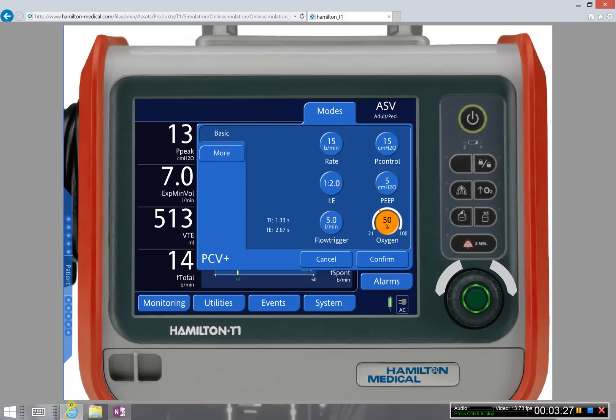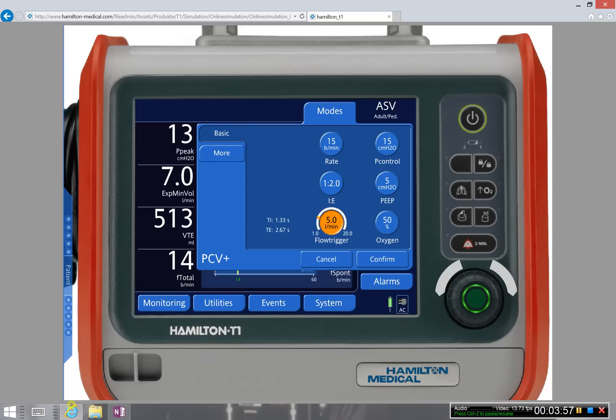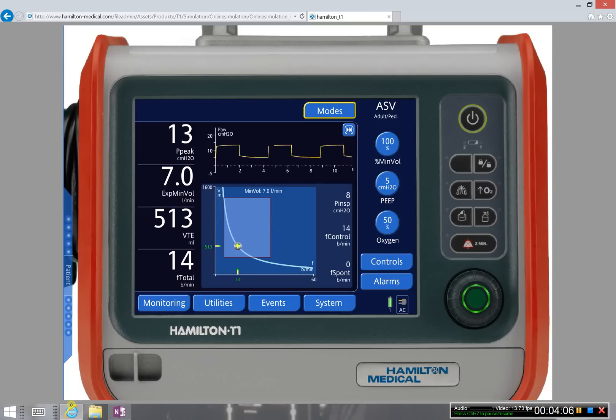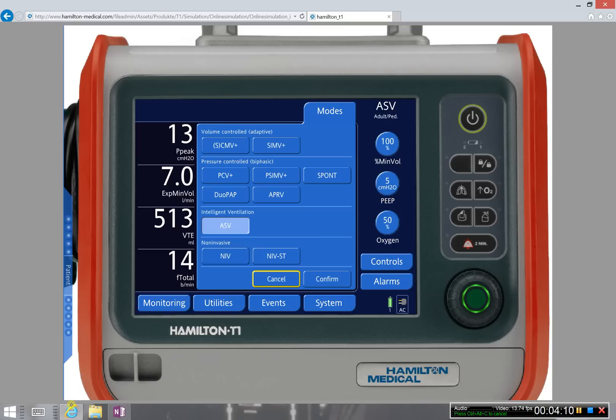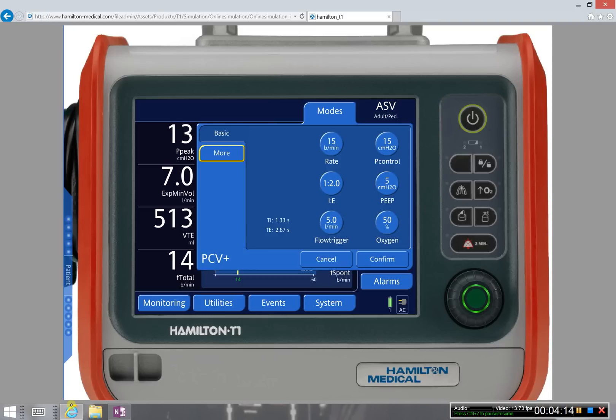The oxygen level can be set to control how much oxygen the patient receives, and depending on your site or policies, you may have specific guidelines for baseline oxygen settings. The flow trigger is a setting that controls when the ventilator senses a breath and delivers a breath depending on a patient's spontaneous effort — so this is not only a time-controlled but also a patient-controlled mode of ventilation. The trigger is important because you want to sense when the patient is trying to initiate a breath. We also control the rate and, through the rate, the inspiratory-expiratory ratio — the IE ratio.